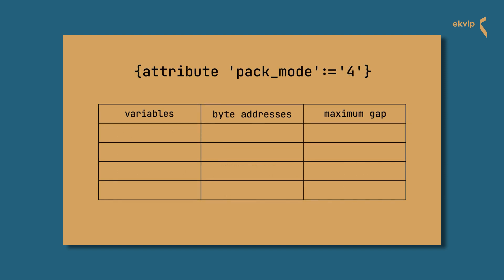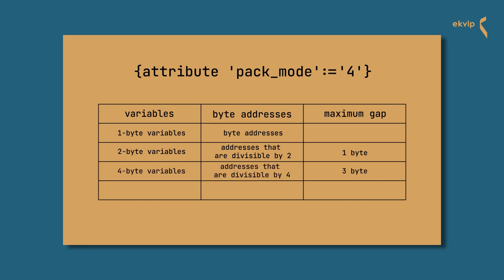If your pack type is 4-byte aligned, then 1-byte variables are assigned to byte addresses, and 2-byte variables are assigned to addresses divisible by 2 with a maximum gap of 1 byte. 4-byte variables are assigned to addresses divisible by 4 with a maximum gap of 3 bytes. And 8-byte variables are assigned to addresses divisible by 4 with a maximum gap of 3 bytes.